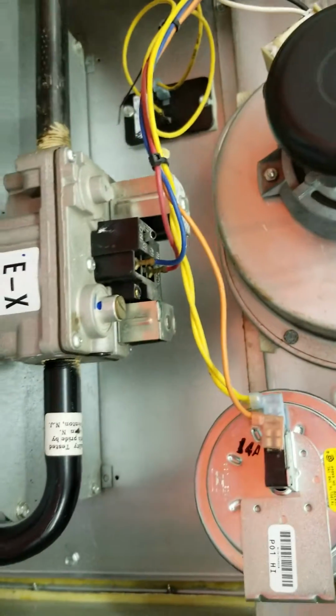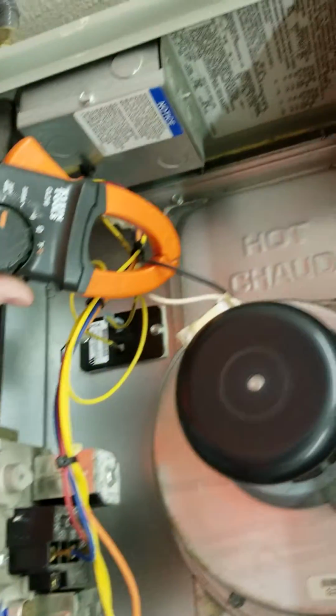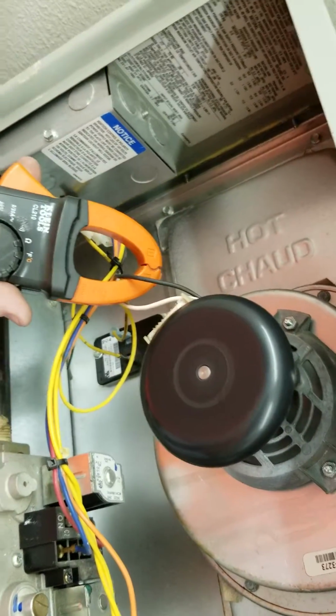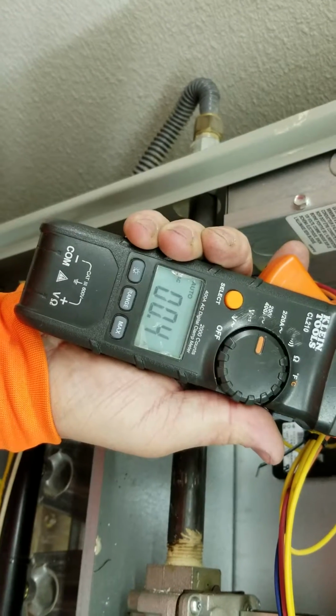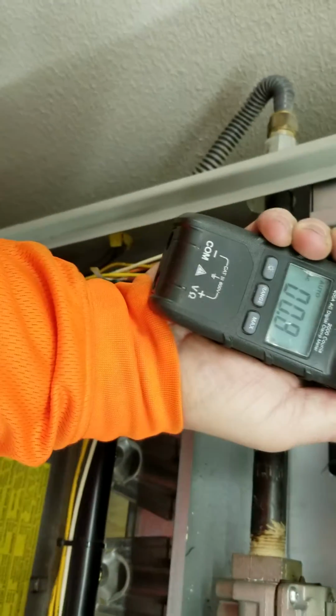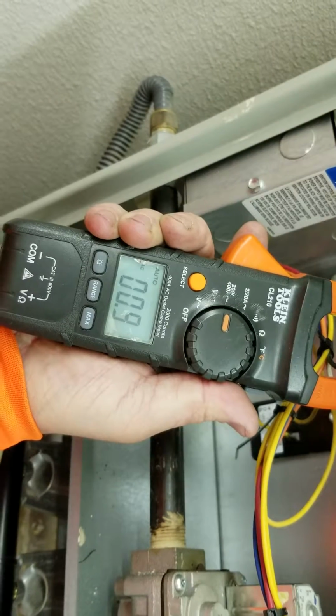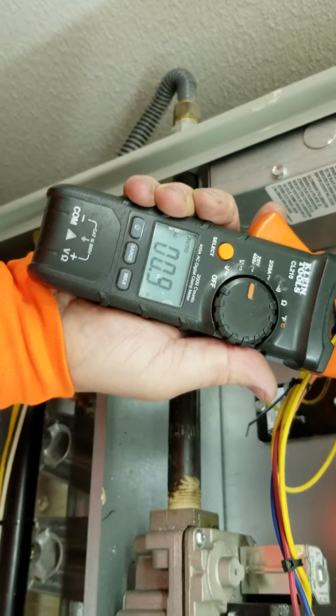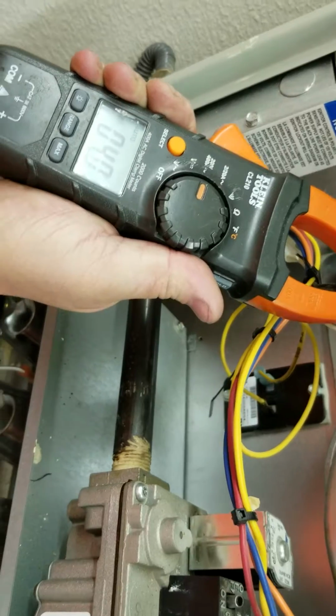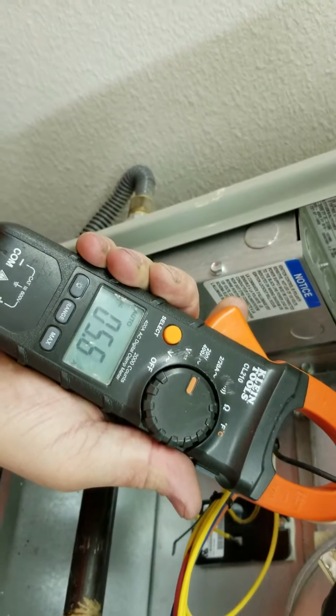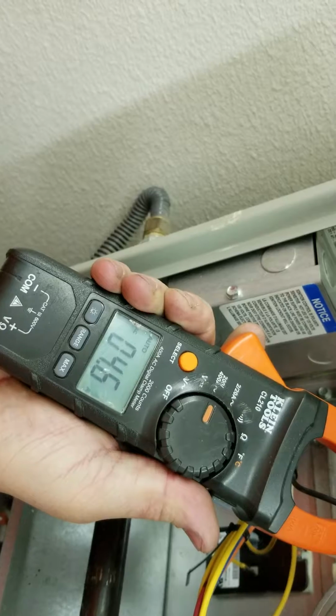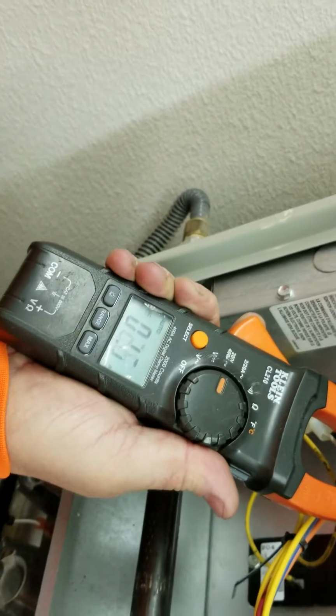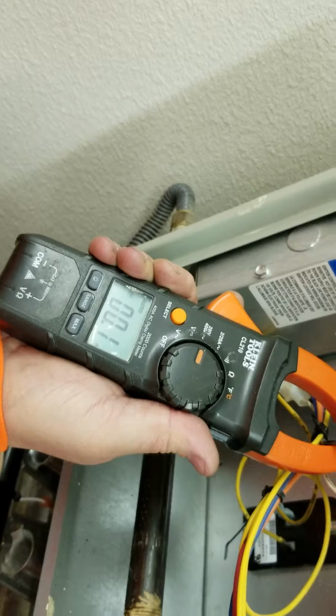Okay, so now the next thing we're going to want to check, we've already done our blower, is to go ahead and check our draft inducer current. And that one, they usually don't read very much. 8 to 9/10 of an amp, 1/10 of an amp. If you get your amp meter too close to the motor windings, it will read all sorts of goofy things, because that motor is inducing more current. So the further away you get it, the more accurate the reading is.